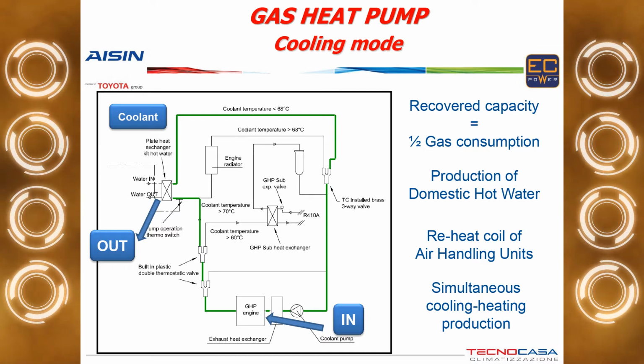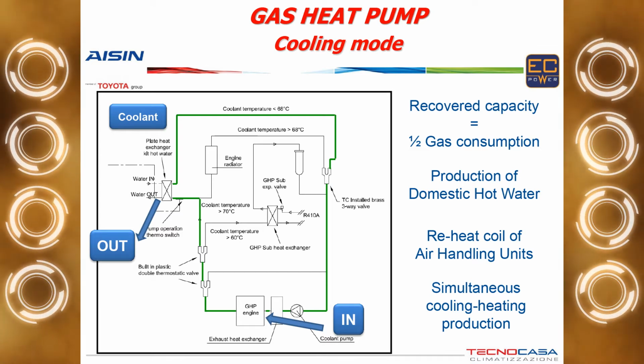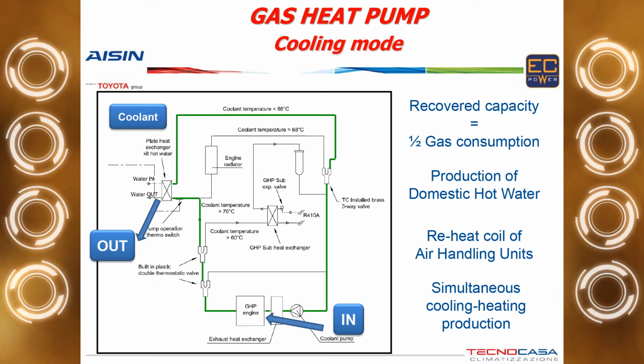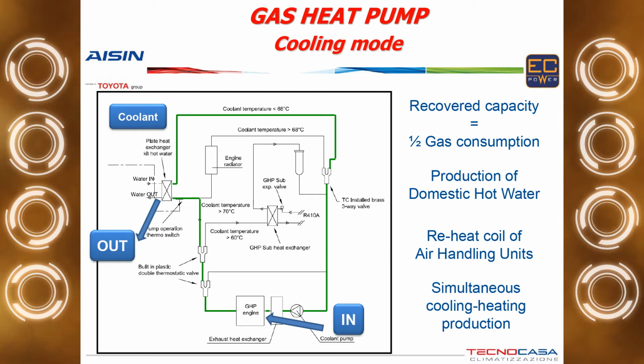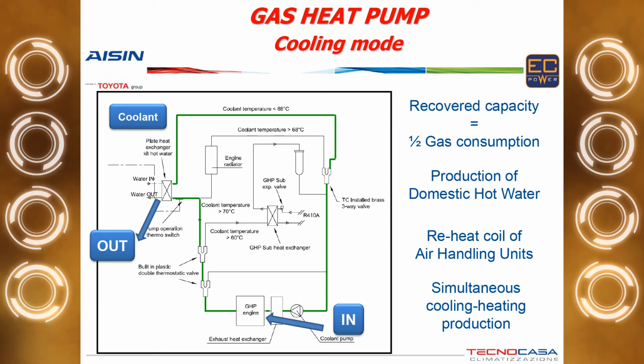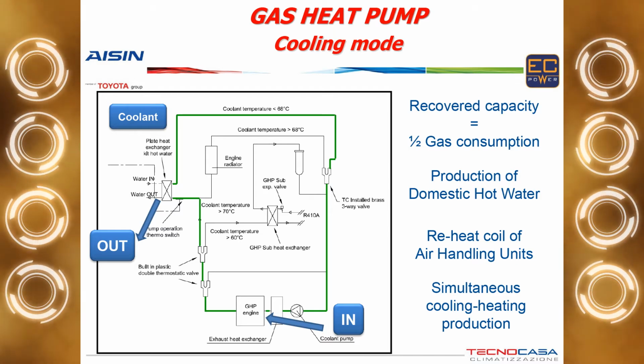So this opens the way to a secondary plate heat exchanger, which is connected to the hot water production on the other side. So basically, instead of using the engine radiator to cool down the engine coolant, we are using a buffer of water to keep the engine down. This also has a positive effect when we are working at very high outside temperatures, because as long as we can keep the engine at the proper temperature, we won't have problems in overheating and damaging the engines. Of course, when the domestic hot water is not needed, we have another thermostatic valve to dissipate the extra heat with the engine radiator.